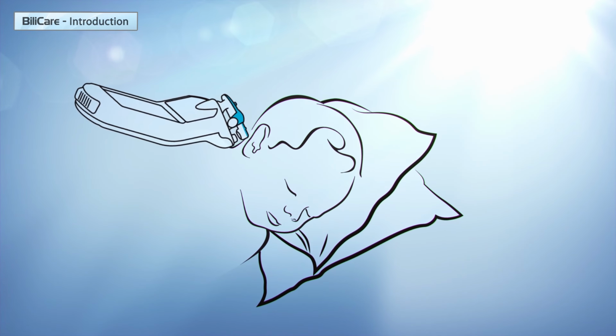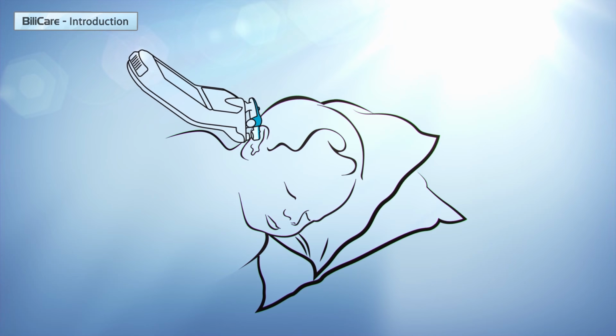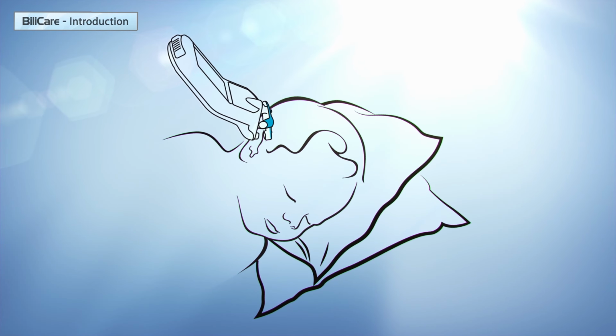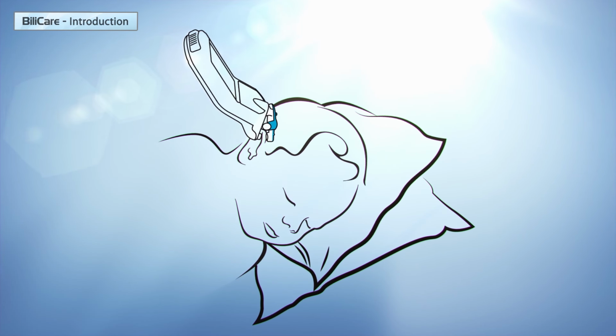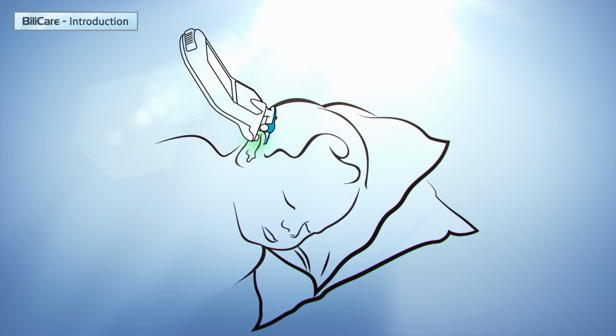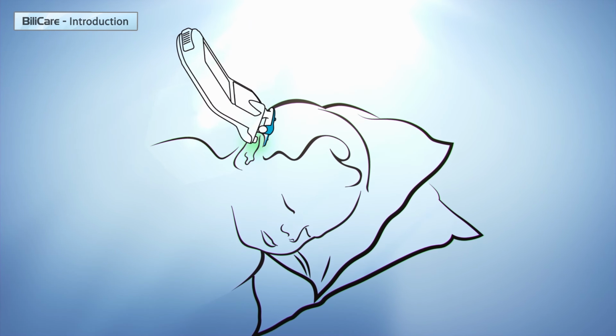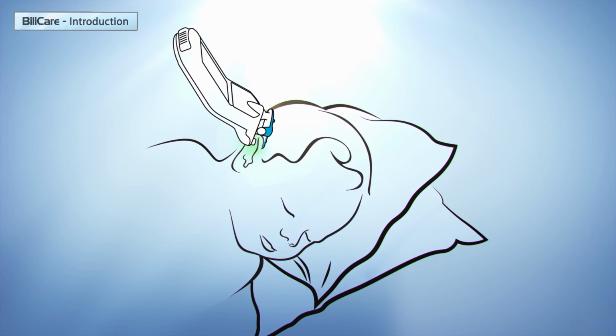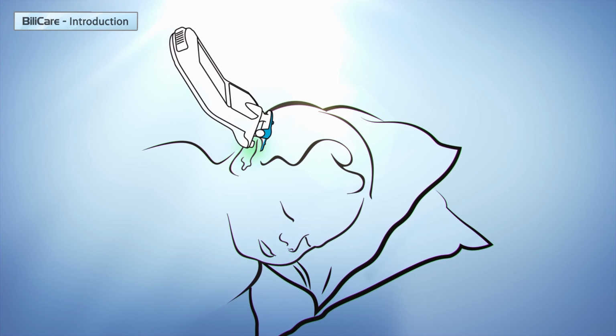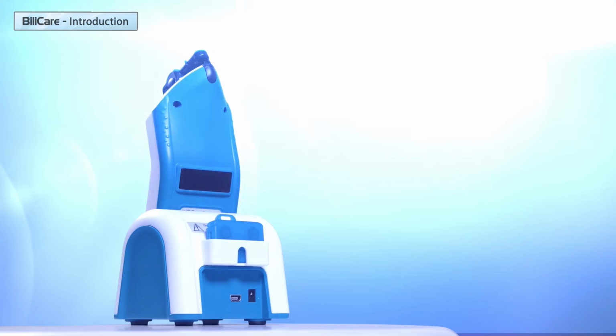BiliCare applies a certain pressure at the point of measurement. Blood in the measurement area may affect the result. Therefore, the blood is literally pushed away from the light path by applying pressure that is a bit higher than the systolic pressure. On the other hand, the pressure is restricted in order not to disturb the baby.